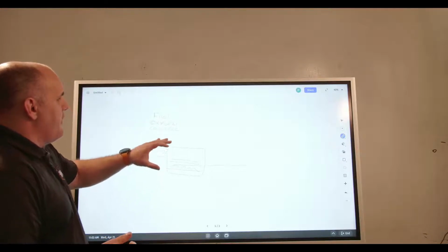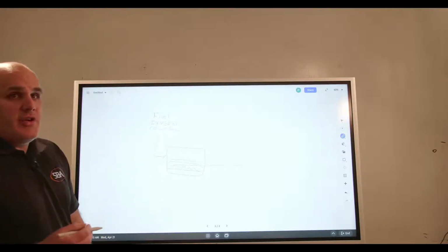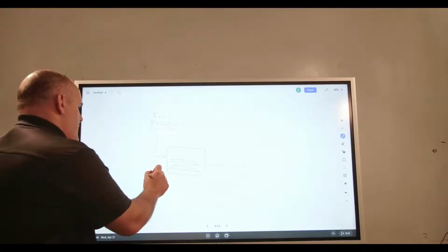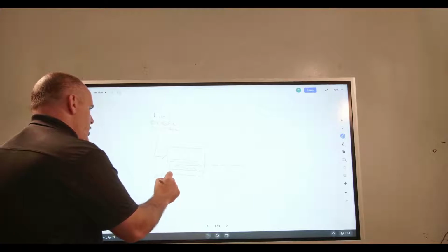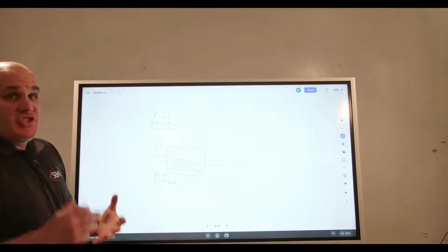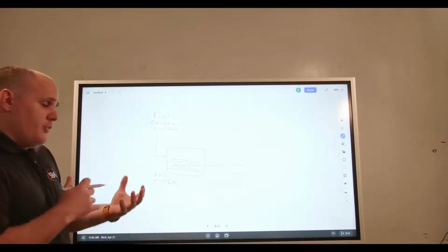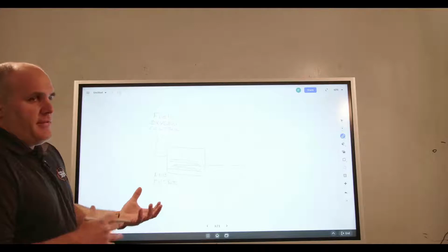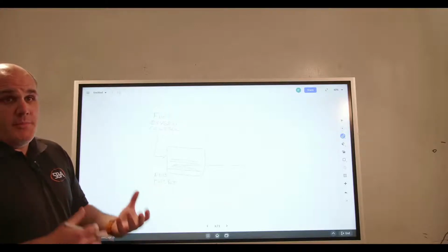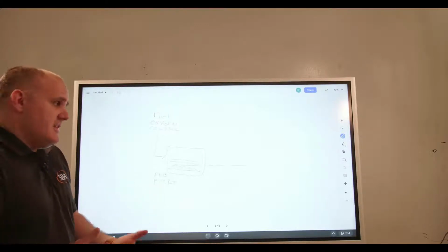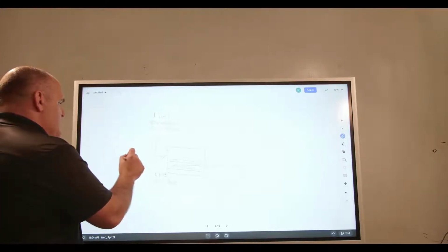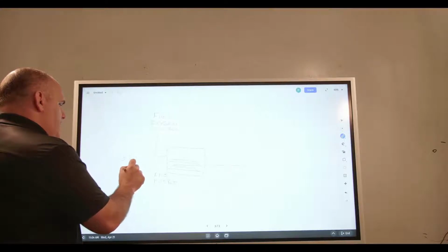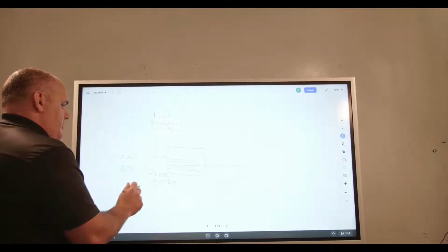So as I was saying, you've got fuel, oxygen, and control. Control is going to be two things. We're going to have our enable, and we're going to have our fire rate control. You don't always have fire rate control, but you almost always have enable. So just like the inverse of chilled water plants, we will typically look at outside ambient or building load calculated in BTUs, and then we will enable the boiler. So we're going to have kind of OAT, or we're going to have a BTU load that is causing this enable to trigger.